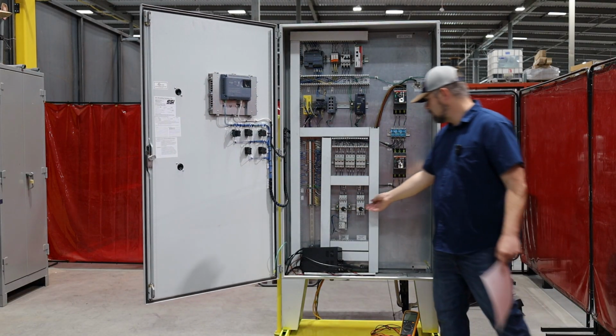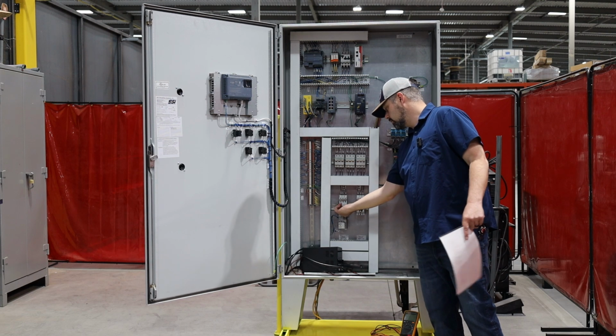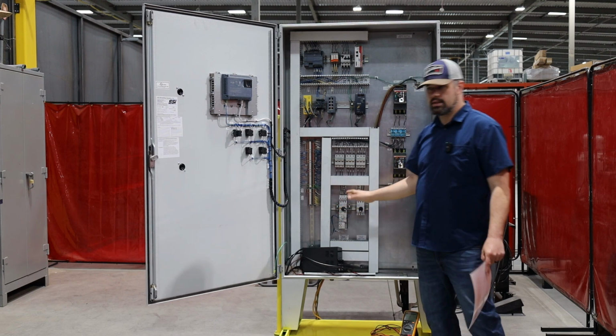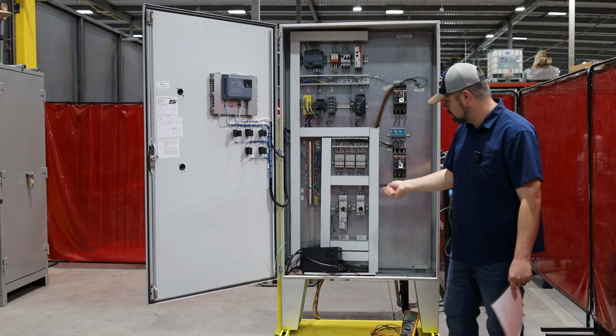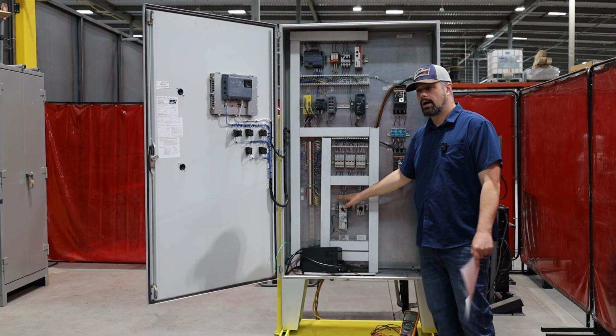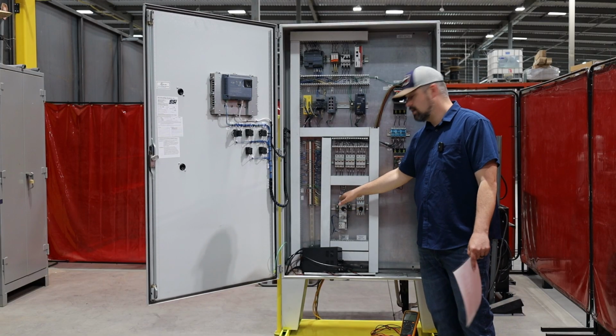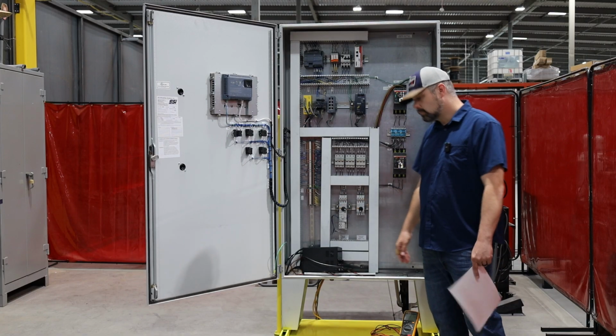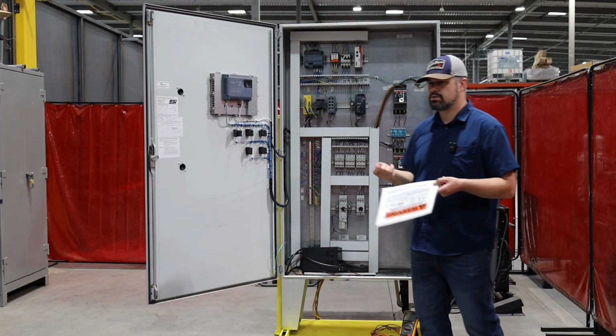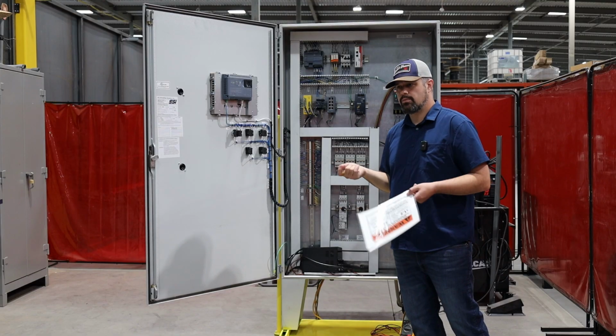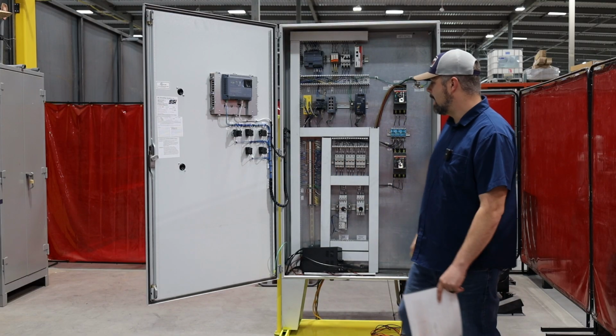We verified and we've seen, let's say, that neither of the breakers are tripped, right? Let's just say they were good. And now we want to take a verification of voltage. We want to actually see if there's voltage coming to this breaker. Okay, so you grab your meter, you've got your PPE on, you can verify the presence of voltage, okay? Now, let's do the other scenario.